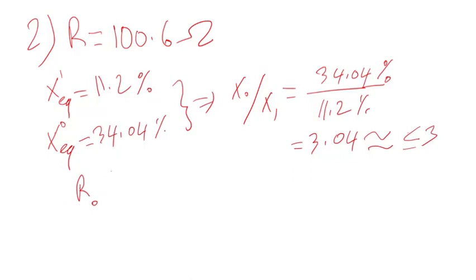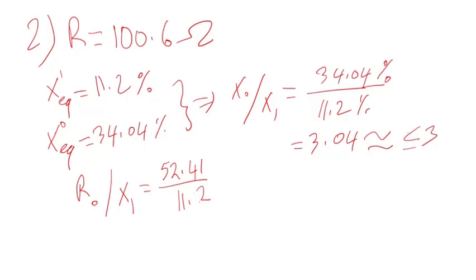Now let's calculate the other ratio: the zero sequence resistance divided by the positive sequence reactance. This is not less than one, so effective grounding is not maintained in this case either.